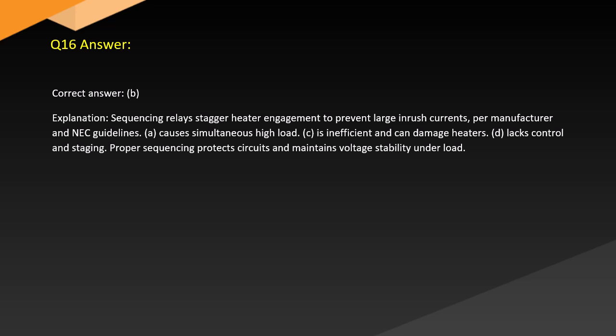Answer. Correct answer: B. Explanation. Sequencing relays stagger heater engagement to prevent large inrush currents per manufacturer and NEC guidelines. A. Causes simultaneous high load. C. Is inefficient and can damage heaters. D. Lacks control and staging. Proper sequencing protects circuits and maintains voltage stability under load.